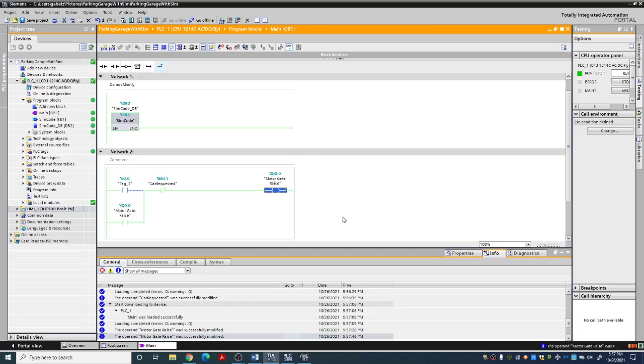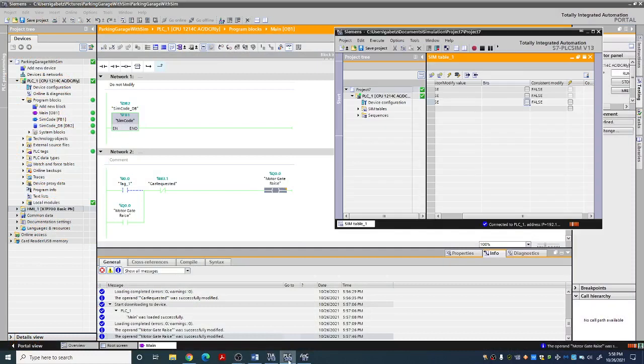And remember, the screen, sorry, not the code, your screen is only updating like every 300 to 400 milliseconds. So you may toggle something, it may go green for one scan of the code and then go back to being false, and you never see it on the screen because your screen is not updating as fast as the code is running. So I just like to point that out to you. So that's how you roughly use the simulators real quick.